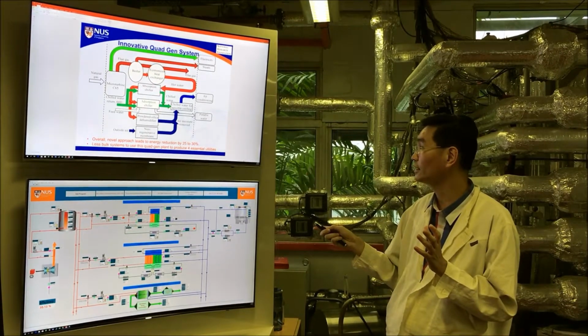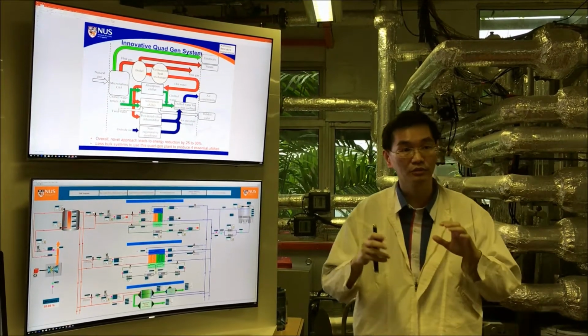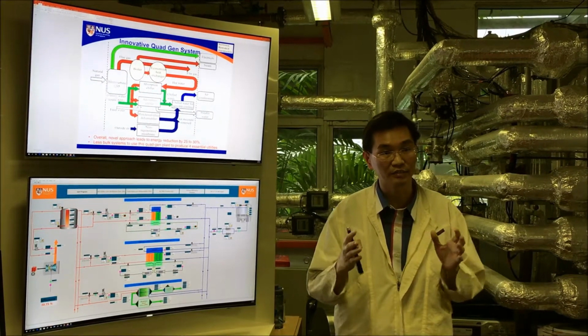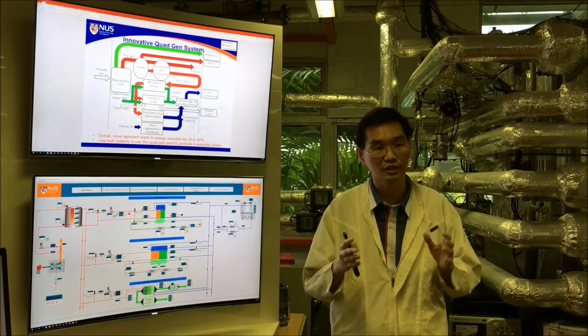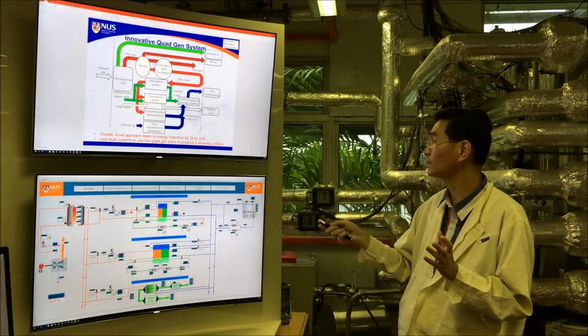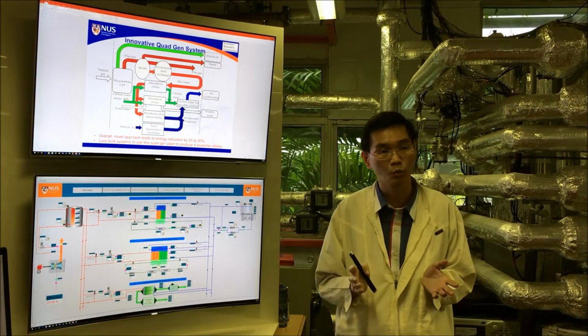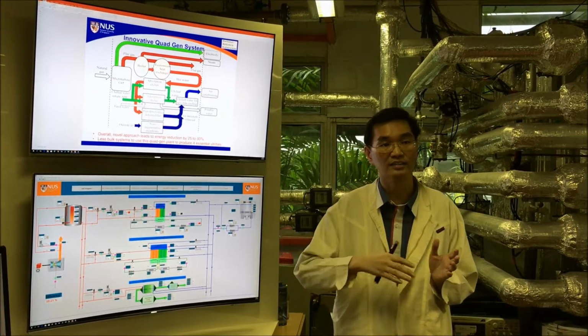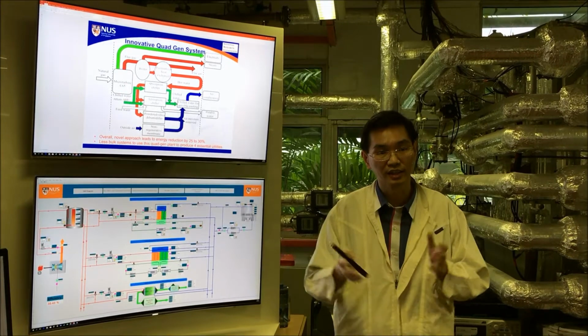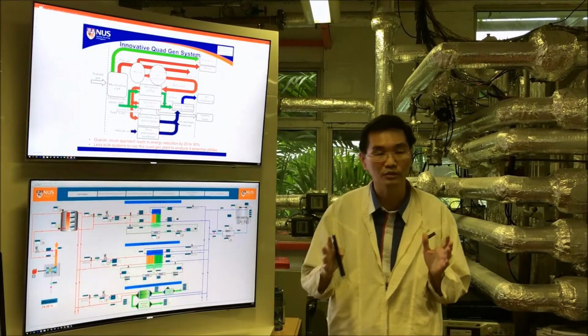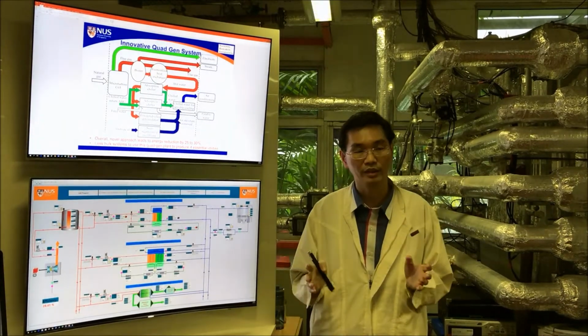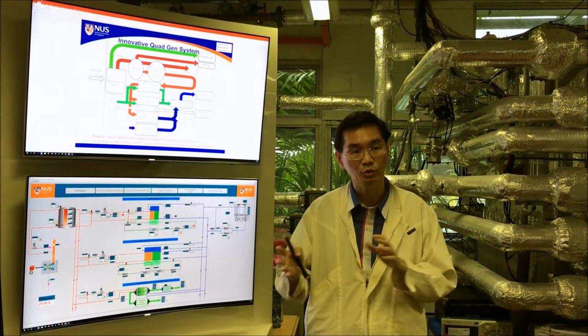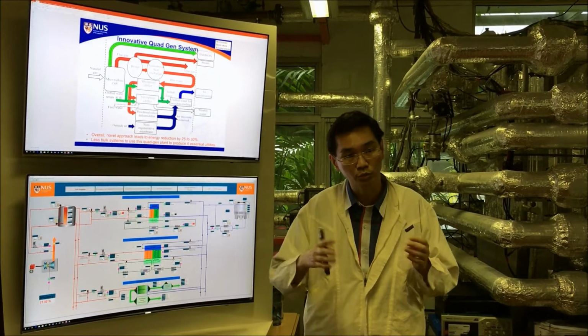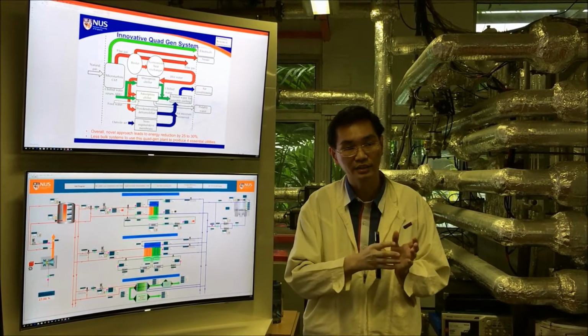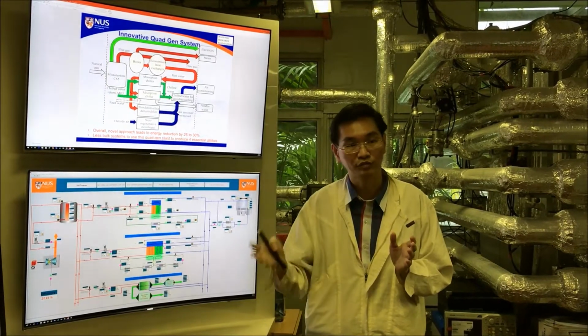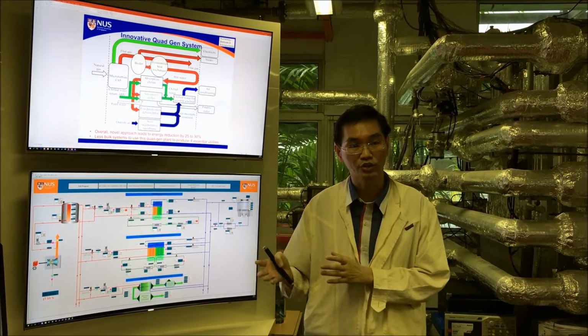After producing the chilled water, the heat that's exhausted from the AB chiller is still good quality. In this case, it's about 70 to 75 degrees. This 70 to 75 degrees waste heat is again used for the second stage of another chiller system. In this case, what we call the adsorption AD chiller, right? As in contrast to the earlier one, which is the AB chiller. This AD chiller is a very unique technology. It's a 4-bed 2-evaporator system, again developed at NUS. This system enables us to take in this 70 to 75 degrees waste heat to produce chilled water at 2 different temperatures, 6 to 10 degrees and 13 to 15 degrees to do air conditioning.